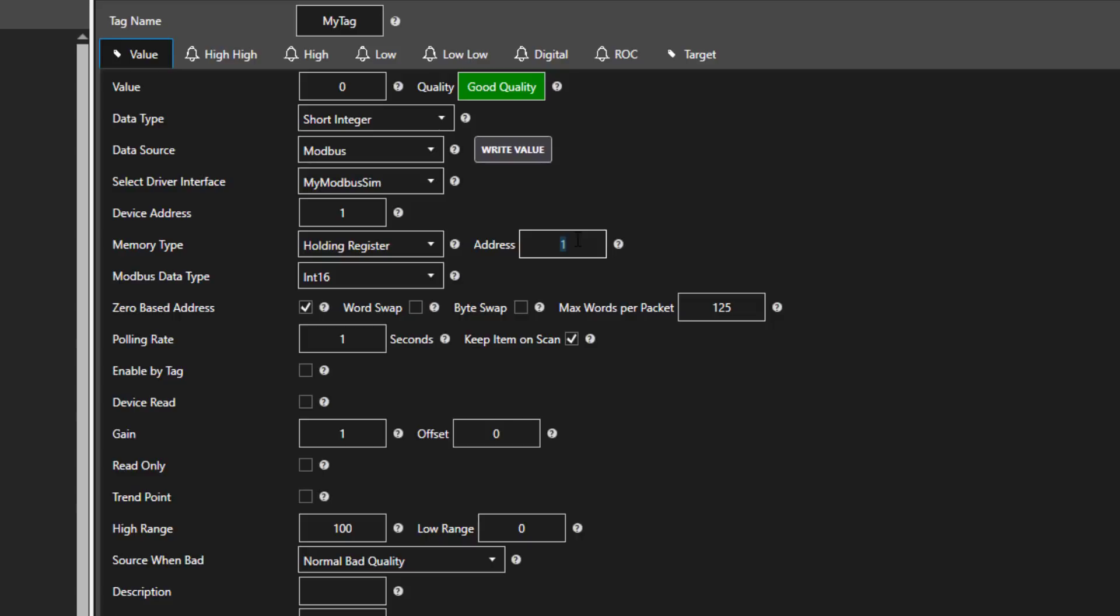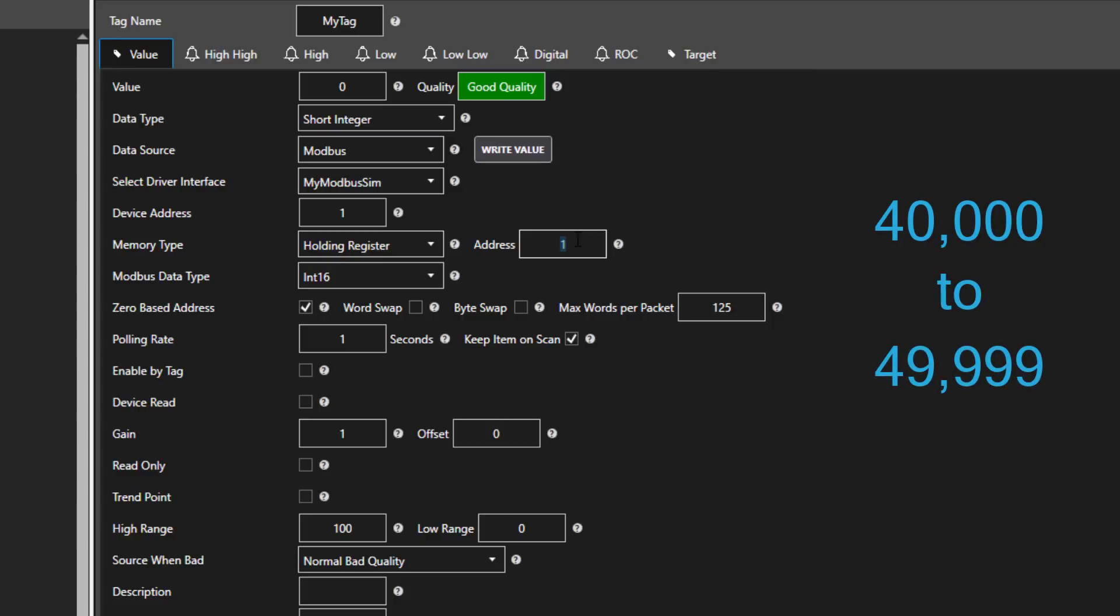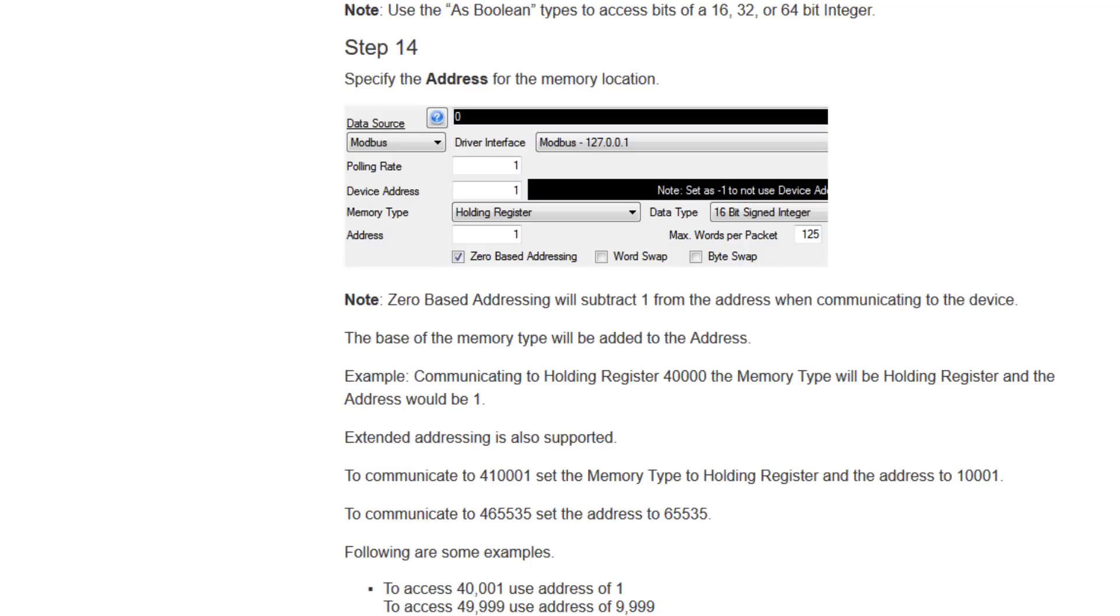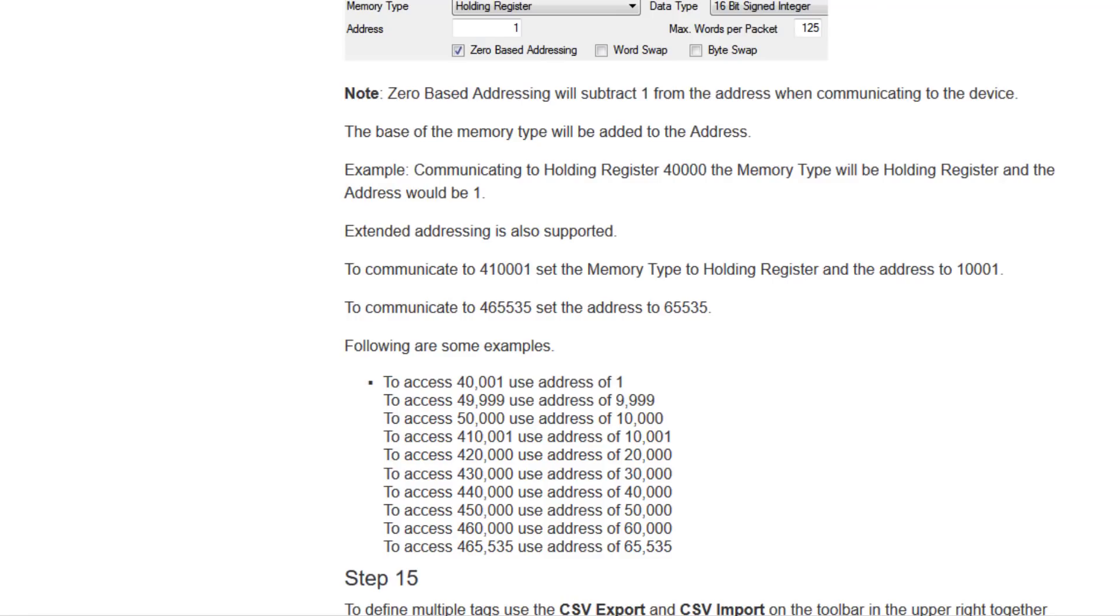The default for holding register range is from 40,000 to 49,999. Step 14 of the article shows some typical examples of both base addressing and extended addressing. If you wanted to access holding register 410,001, you would simply enter 10001 in the address field. In this way, you can access the extended addressing up to 465,535.